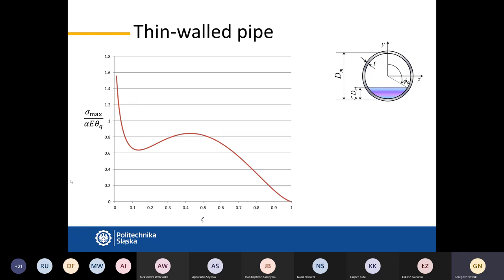Big angle close to 180 meant that we have very little liquid. Here for zeta, the magnitude close to zero means that we have very little liquid. So for very little liquid, only a small fraction of the pipe has significantly different temperature than the other, and it will be observed as high stresses occurring.